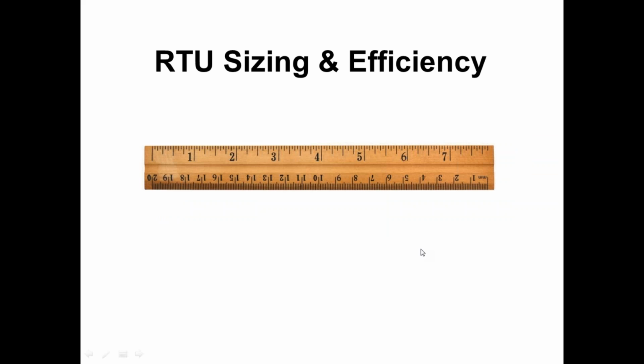All right, so let's talk about stuff that's specific to rooftops that are in this code. The first thing is you're not going to find a section of the code called rooftop units. In fact, you probably won't even find the word rooftop units. As far as the code is concerned, rooftops are basically DX packaged HVAC units, but you won't find a section for that either. You have to go read all of the individual sections and decide which of them apply to a rooftop. Because unlike a boiler or a chiller or something like that, a rooftop is doing lots of things. It's doing your ventilation air, so it's got outside air intakes, it's doing your cooling, it's doing your heating, so it's got lots of components all in one box. So the pieces of what you have to do are scattered all over the code.